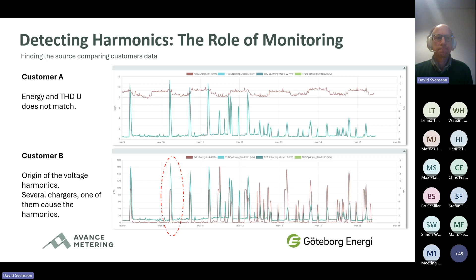Imagine a customer complaining about expensive equipment failures, only to discover that it was their own charging station polluting the surrounding grid with harmonic distortion. By analyzing the energy consumption patterns and voltage harmonics, we could pinpoint the source. But as we all know, these filters can degrade over time, allowing the harmonics to resurface. Following measurements over time will give you valuable insights about actions taken by the customer.